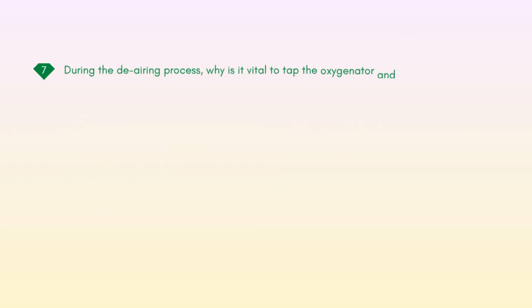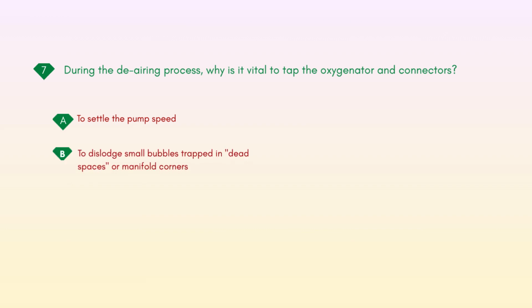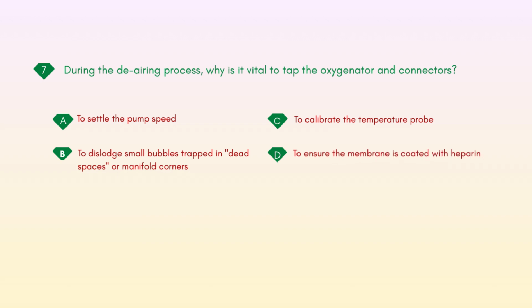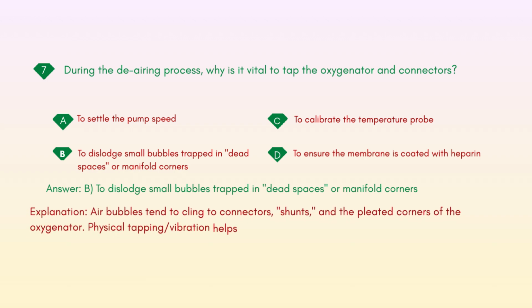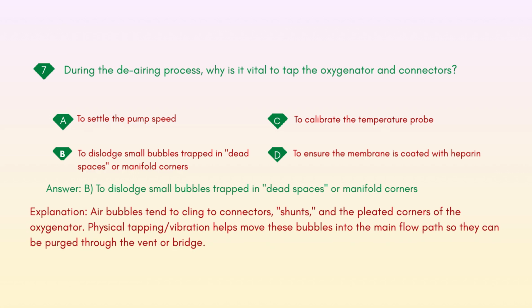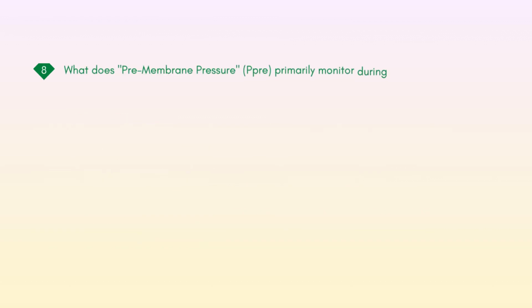During the de-airing process, why is it vital to tap the oxygenator and connectors? A. To settle the pump speed. B. To dislodge small bubbles trapped in dead spaces or manifold corners. C. To calibrate the temperature probe. D. To ensure the membrane is coated with heparin. Answer: B. Explanation: air bubbles tend to cling to connectors, shunts, and the pleated corners of the oxygenator. Physical tapping/vibration helps move these bubbles into the main flow path so they can be purged through the vent or bridge.